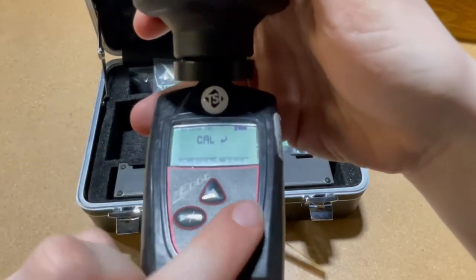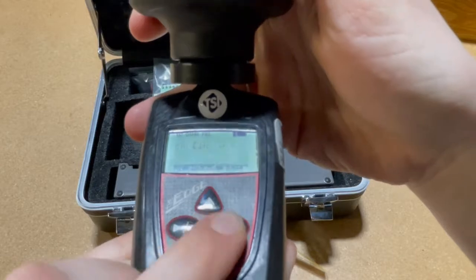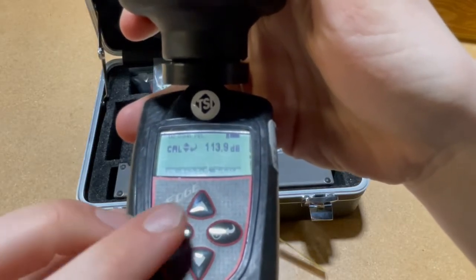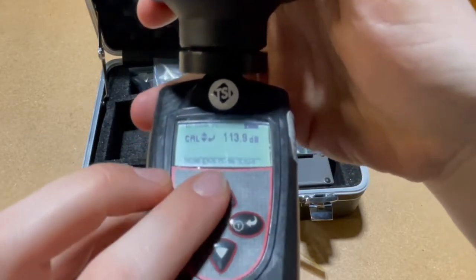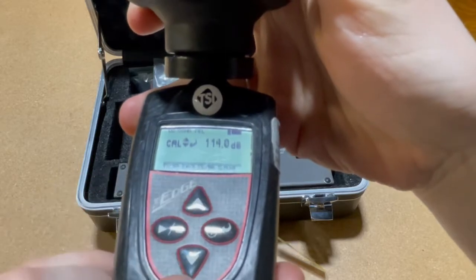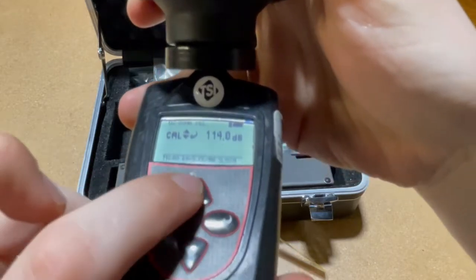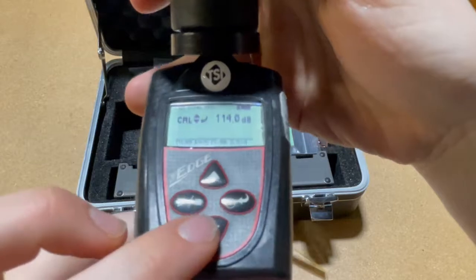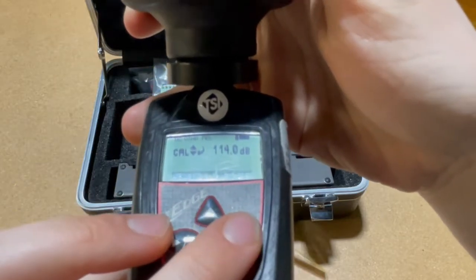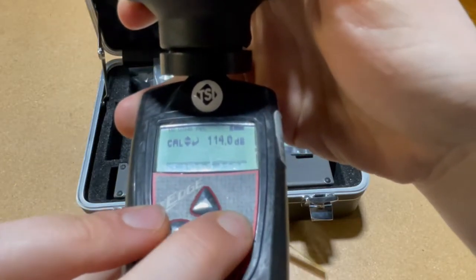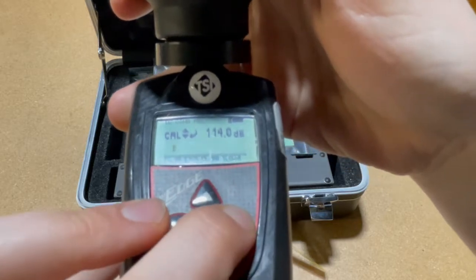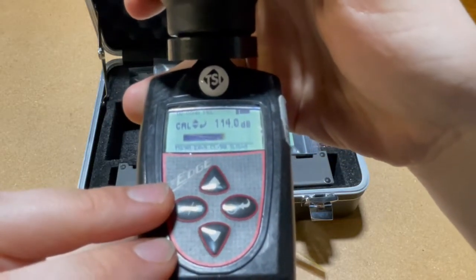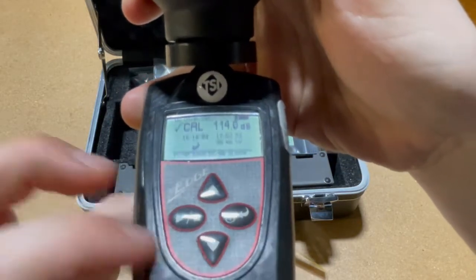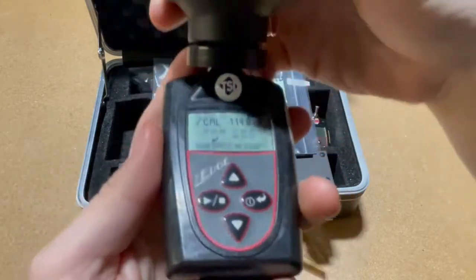There it is. So we're going to hit this right button. You want to calibrate it to 114 decibels. You can move the amount up and down using these arrows if it is not at 114 when you go to calibrate it. So once it's at 114, we're going to hit the cal button again right here on the right. And then it's calibrated. Now we can remove the QC10.